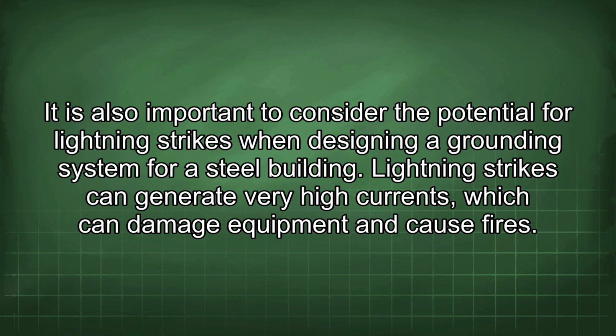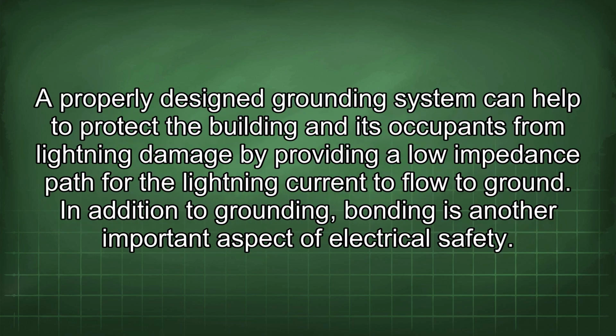It is also important to consider the potential for lightning strikes when designing a grounding system for a steel building. Lightning strikes can generate very high currents, which can damage equipment and cause fires. A properly designed grounding system can help to protect the building and its occupants from lightning damage by providing a low impedance path for the lightning current to flow to ground.